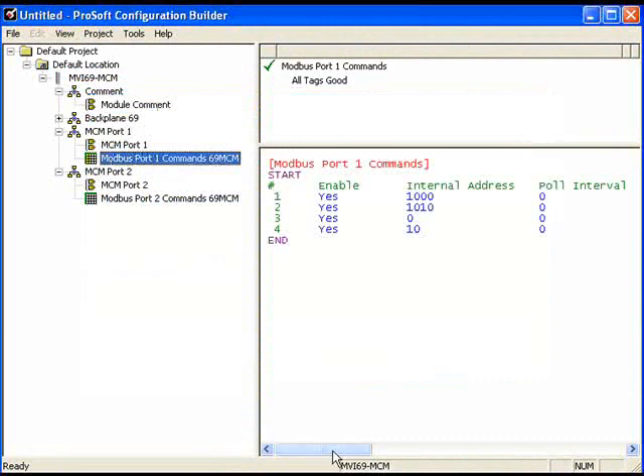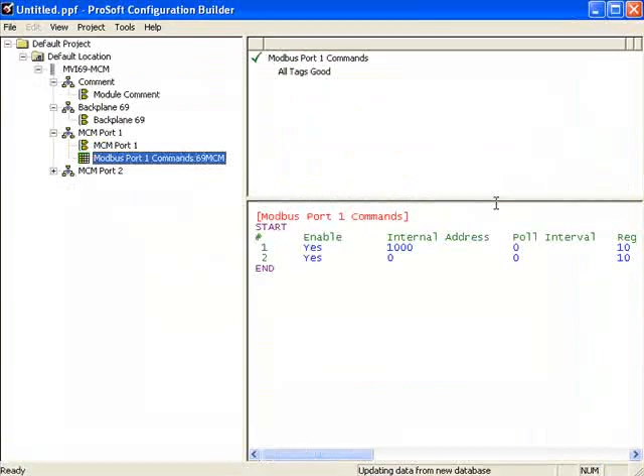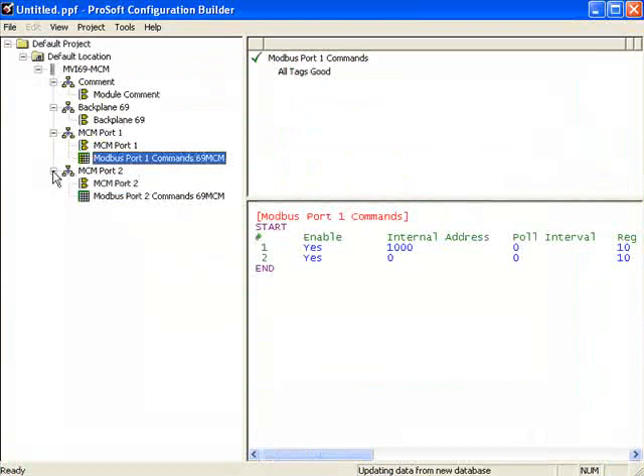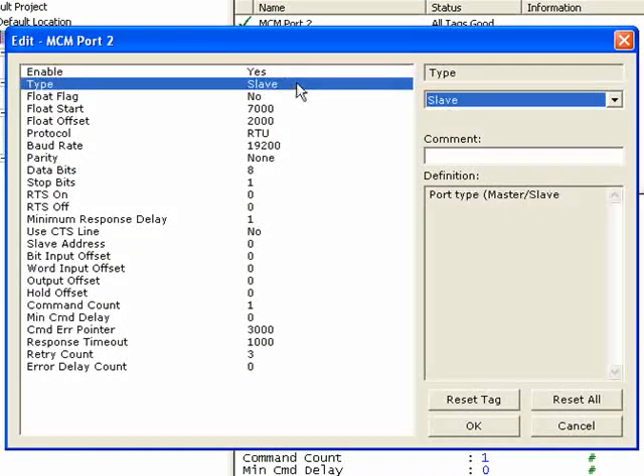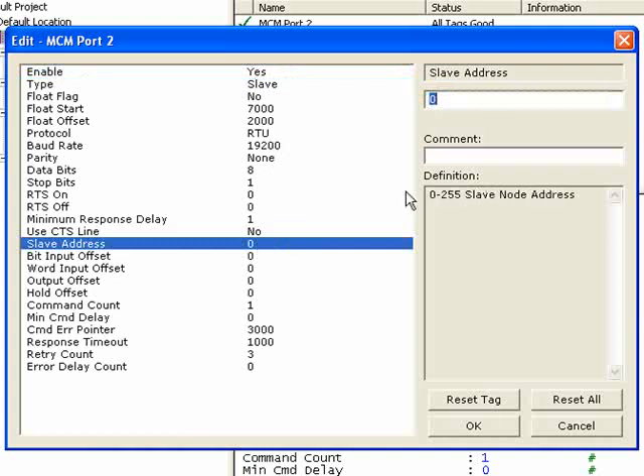Now as we drag over, we can see how our commands are laid out. I'll go ahead and open up port 2, and we're going to set port 2 as a slave. I'll leave all the parameters the same except for the slave address — since it is a slave, it does need a slave address. I'll set my slave address to 10. If there are any settings you're not familiar with, read the definition as well as the MVI69 MCM user manual. What's nice about being a slave is there are no Modbus commands to configure — since the port's a slave, there are no master commands.